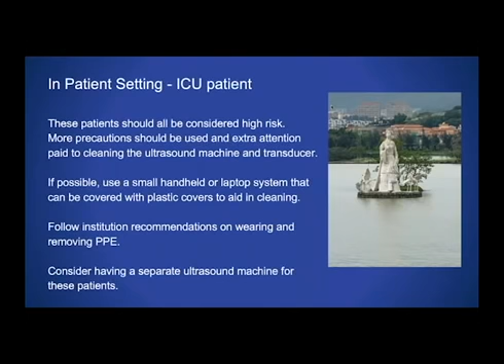We went over transducer cleaning a lot, but I just want to highlight that all cracks and crevices need to be cleaned, as well as the cable if it's touched the patient. If you cannot remove the gel with paper towel or cloth, you need to take the probe off and wash it with soap and water, and then use the low-level disinfectant. If you need a sterile probe cover and do not have one, you can use a sterile glove.